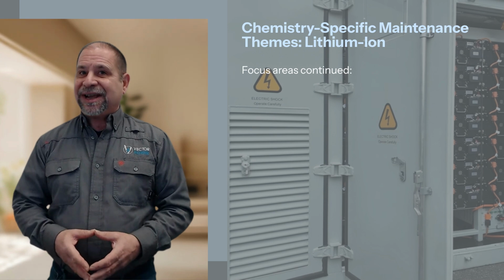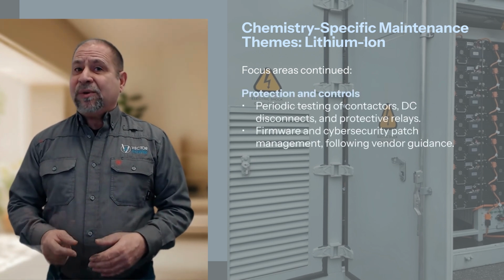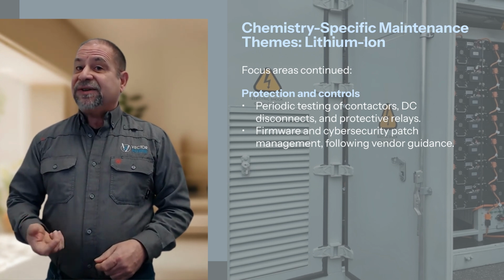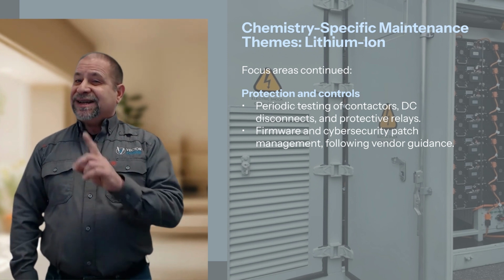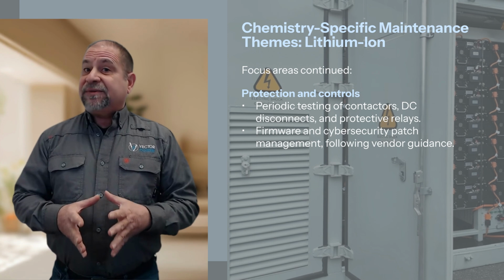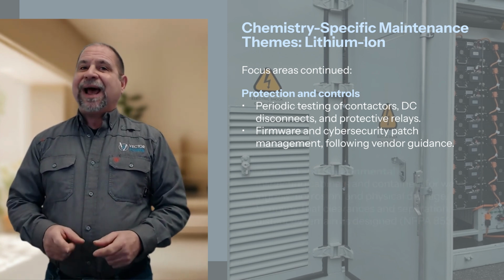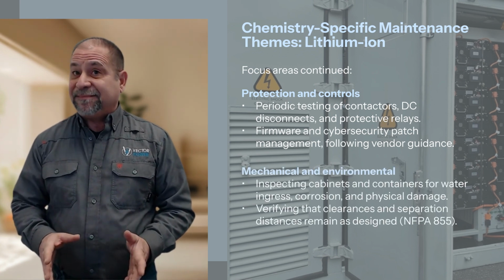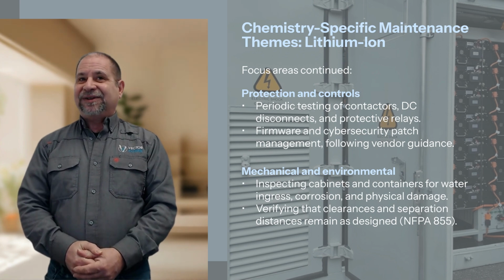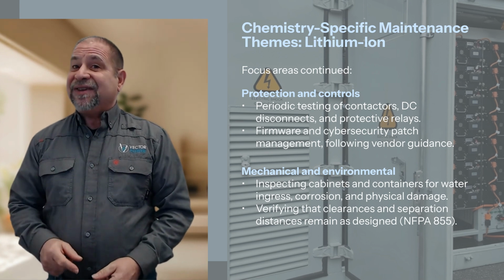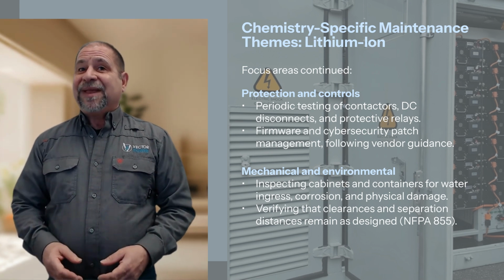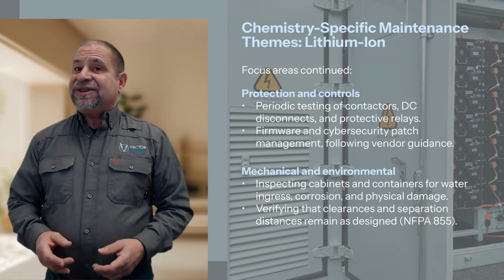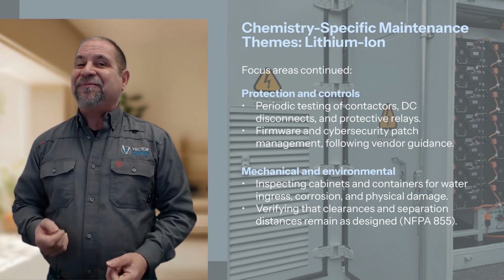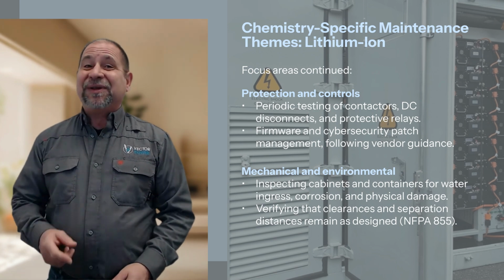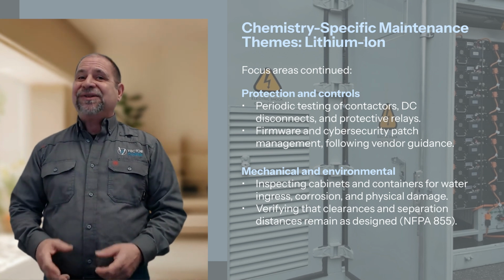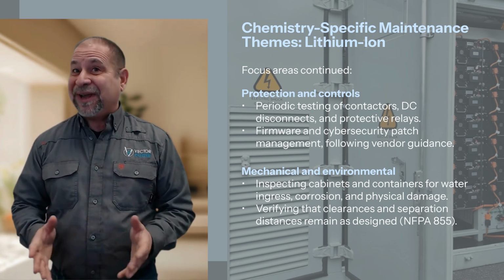Important focus areas continued: protection and controls. Conduct periodic testing of contactors, DC disconnects, and protective relays. Firmware and cybersecurity patch management following vendor guidance. Mechanical and environmental areas of focus. Inspecting cabinets and containers for water ingress, corrosion, and physical damage, and verifying that clearances and separation distances remain as designed, NFPA 855. When dealing with lithium-ion energy storage systems, hands-on work inside modules is typically limited to OEM service.